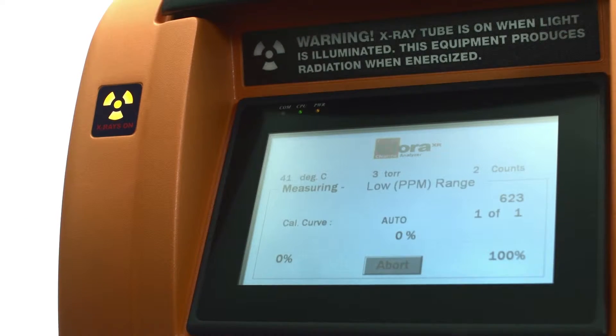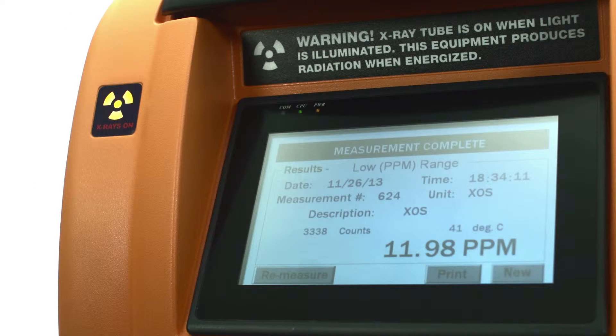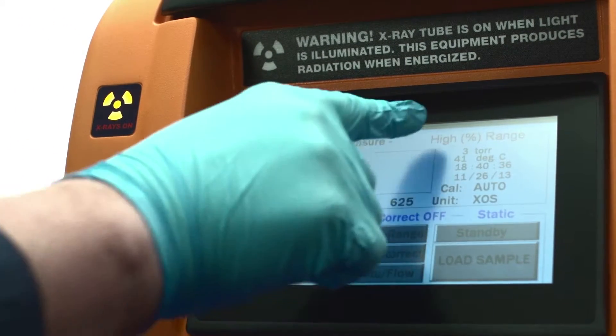The measuring screen provides you with a status bar as the analysis progresses. In a matter of minutes, your results are in. Like all XOS benchtop analyzers, the Clora also allows you to measure from sub PPM level up to percent weight levels.